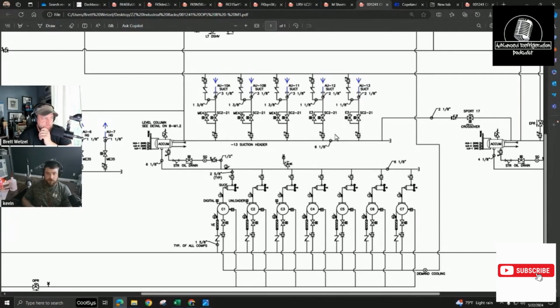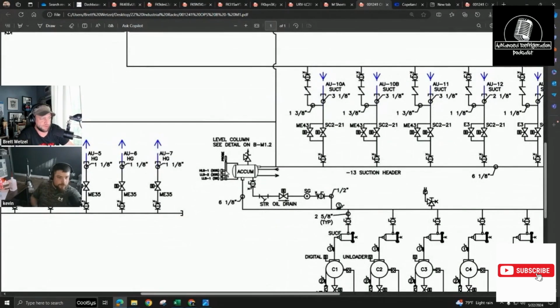If you start seeing header temp spikes or pressure spikes, it's from that. It's there to keep the rack from getting smashed with liquid and hot gas after a defrost. They work fairly well and they keep compressors from cycling. So that's one thing to keep an eye on. This is probably a bad representation of how big this thing is, but this is an accumulator they have on here. If you have an accumulator with 3 different sight glasses and a Hansen probe on there, that tells me right off the bat the accumulator is probably huge. And then you've got an oil drain. The thing's big.